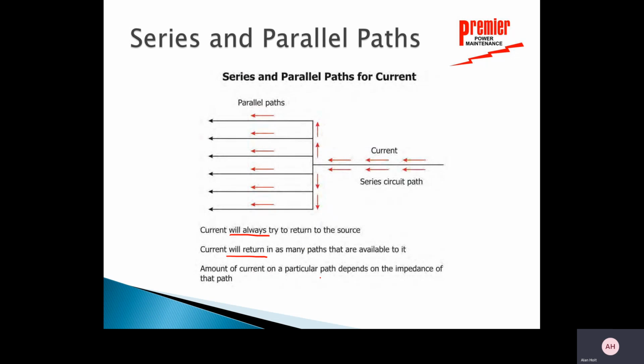Now, the amount of current on a particular path depends on the impedance or the resistance in ohms of that path. So the higher the resistance, the less current is going to go through that section. So that's a precursor for what we're going to talk about when we start talking about this National Electric Code, Article 250, for grounding.